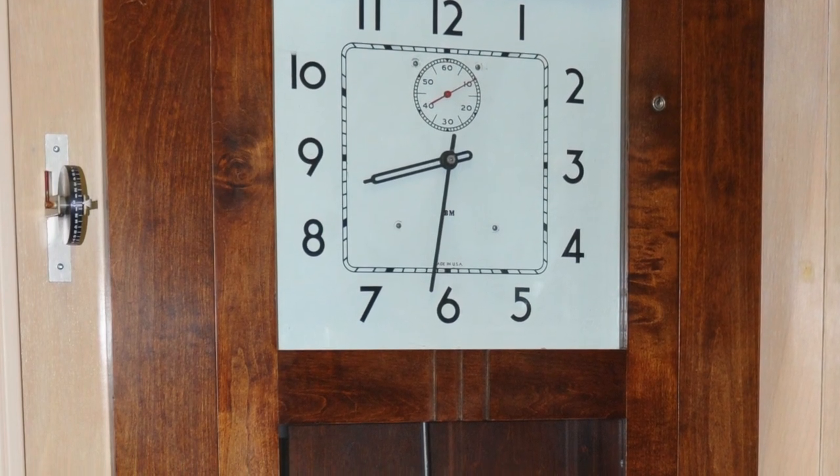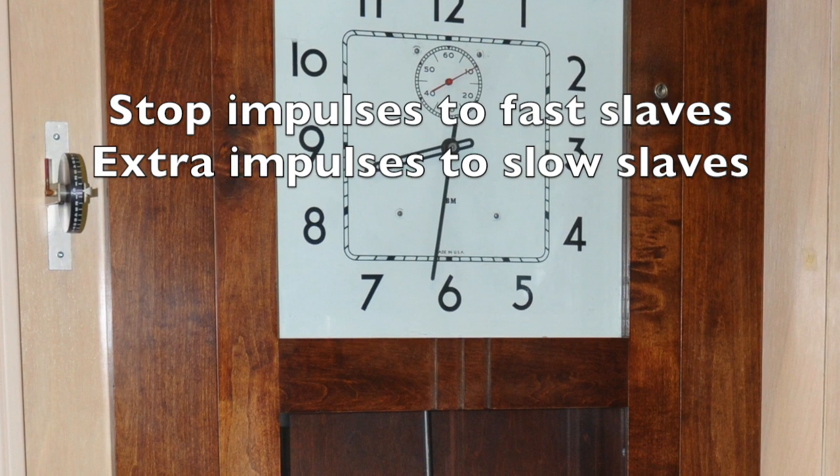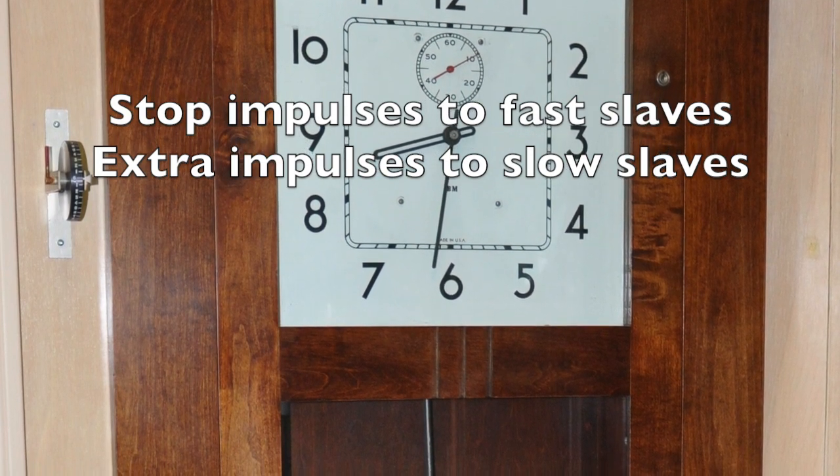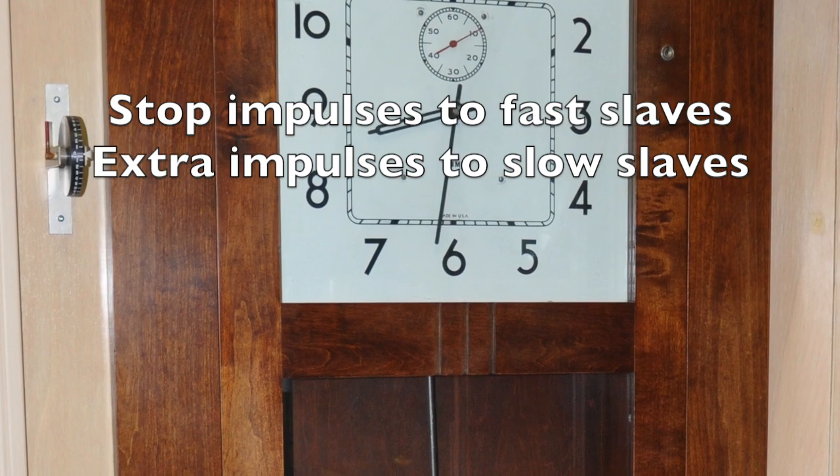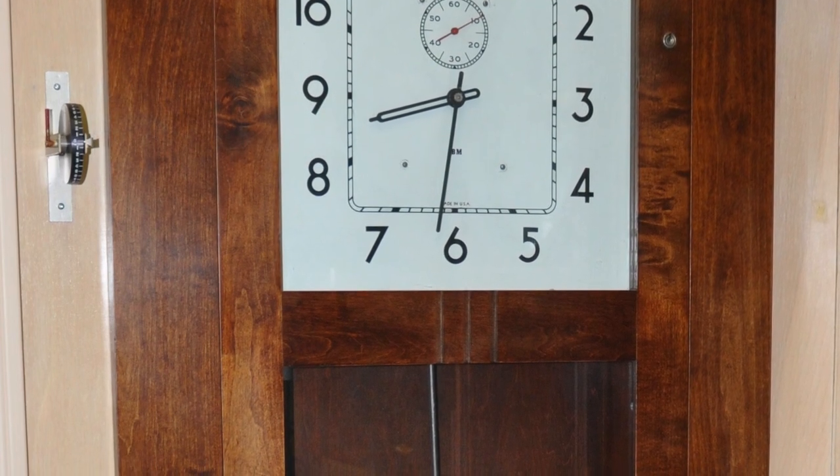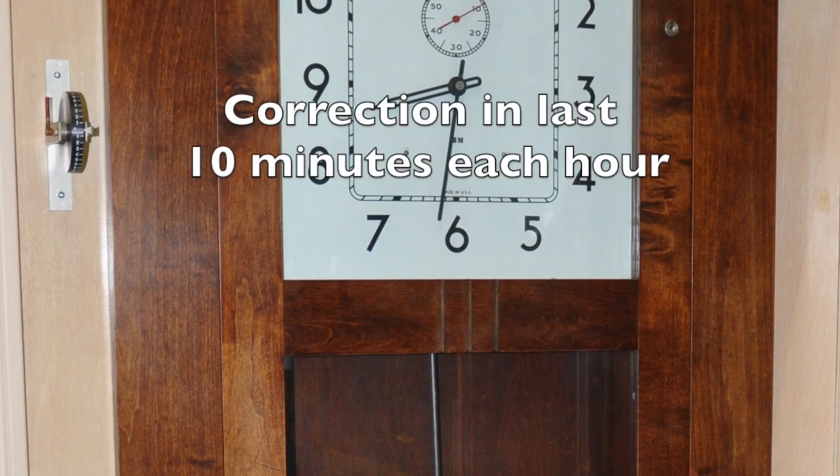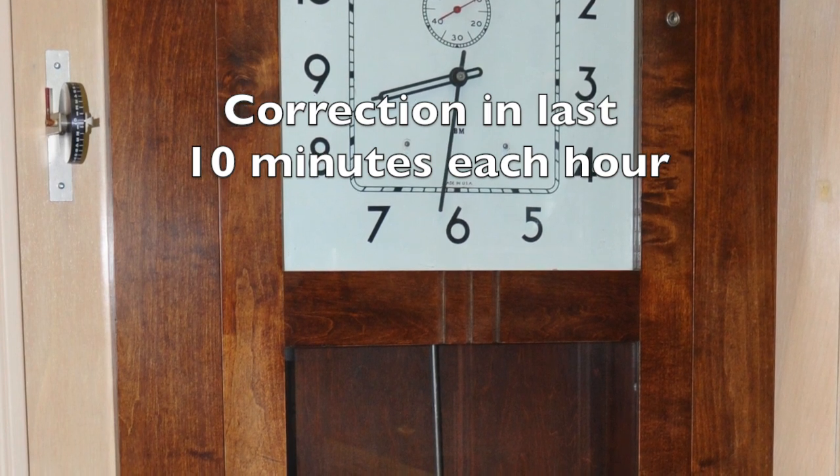Two different lines make it possible for the master to stop impulses to slaves that are fast or send extra impulses to slaves that are slow. The master correction process takes place in the last 10 minutes of each hour.